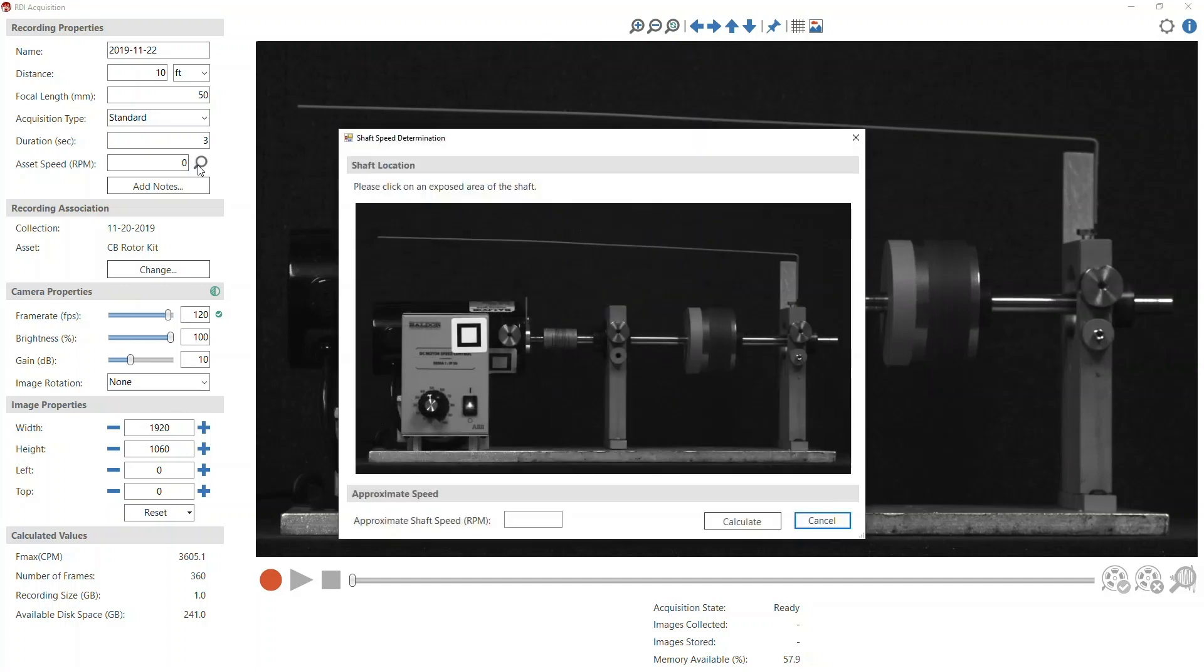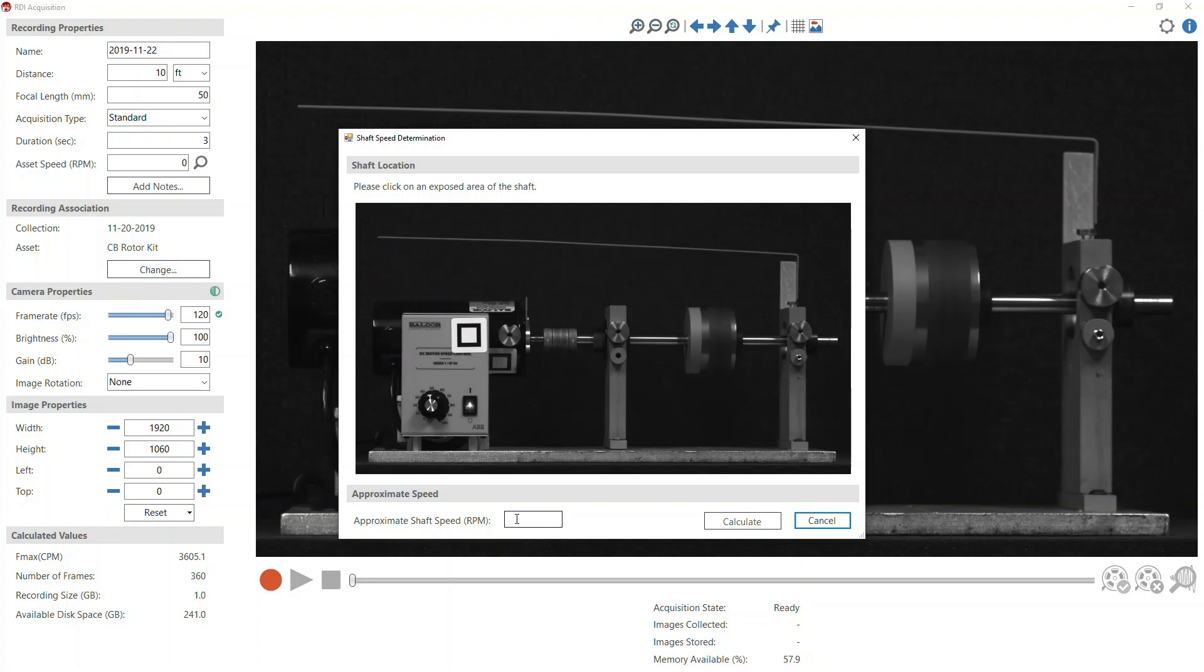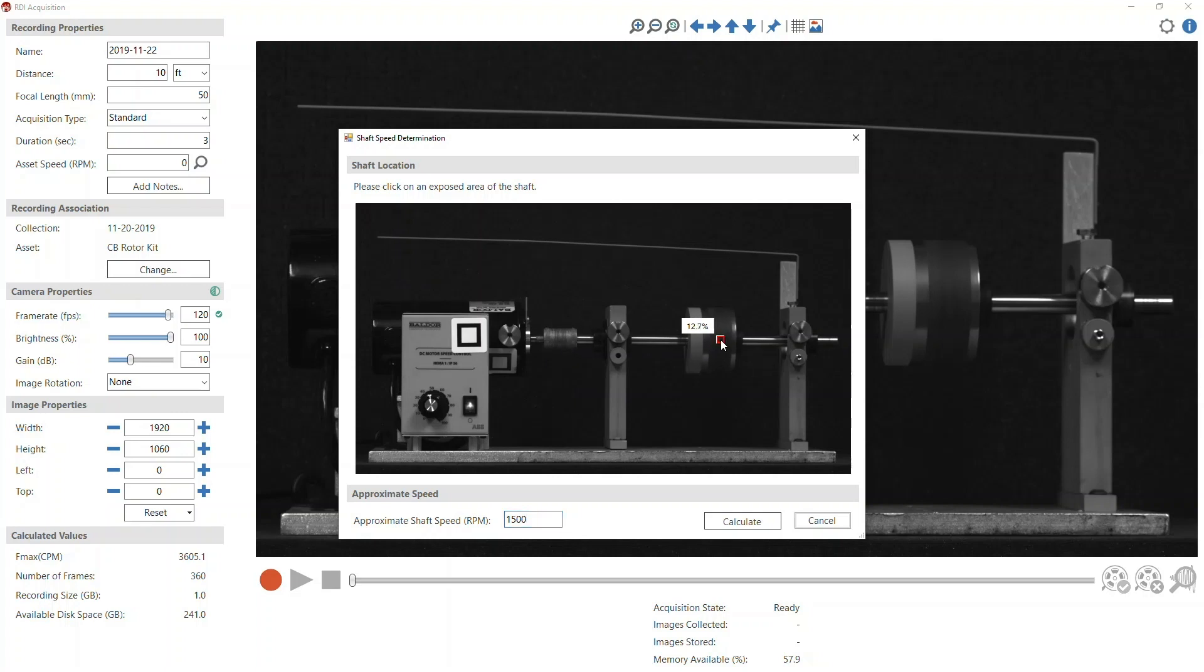To use the RPM measurement tool, click the Calculate Speed button next to the Asset Speed field. This will open the Shaft Speed Determination window. Next, enter the approximate RPM in the approximate shaft speed field. This value should be within 10-15% of the actual RPM.